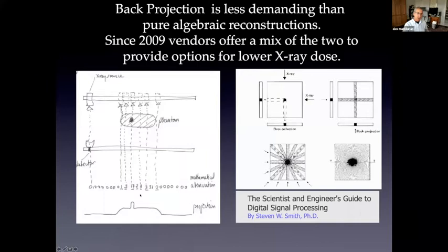So this is kind of a rudimentary drawing of how back projection works. We have an x-ray source and detector, and so we get these values that we collect. If we have a phantom where we have something of relatively high attenuation here and lower attenuation out here, these are the values that we determine. So if we work with the projection data, you overlay the different views, and we get this rough approximation of this object by using projection.